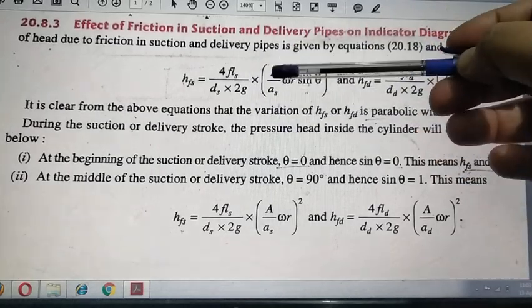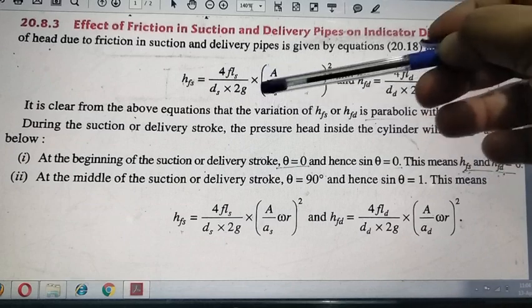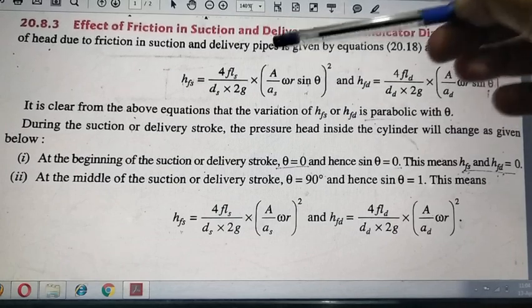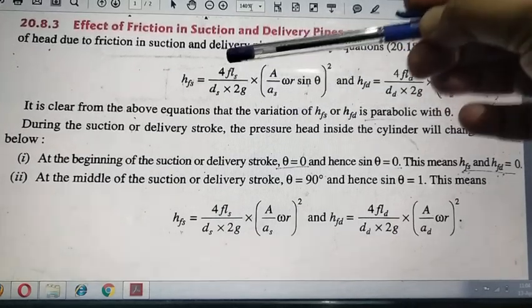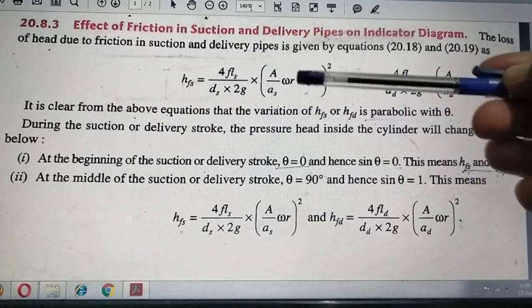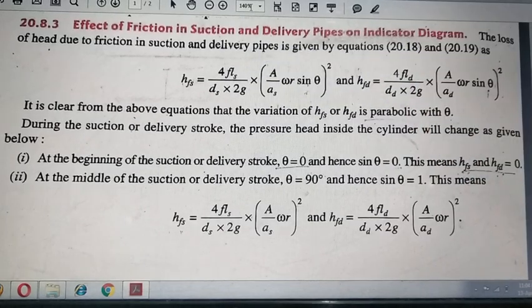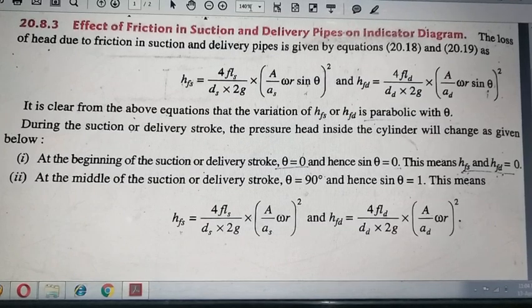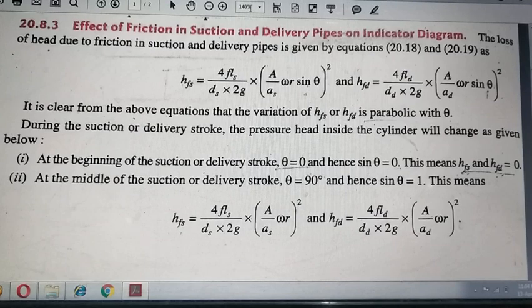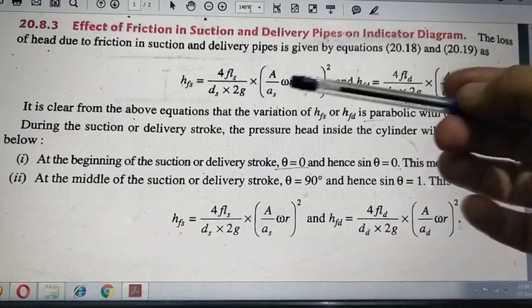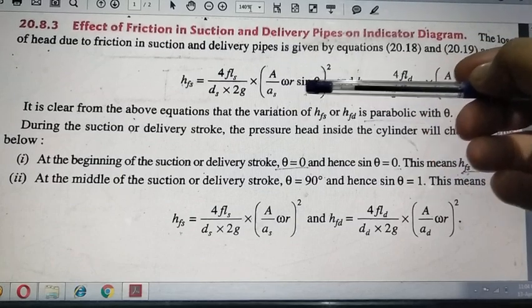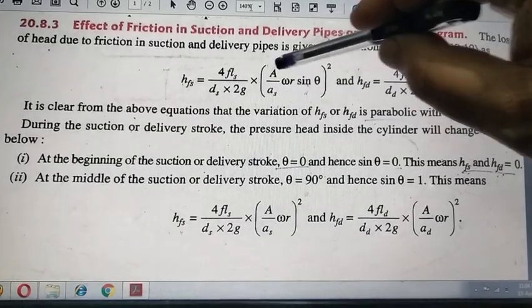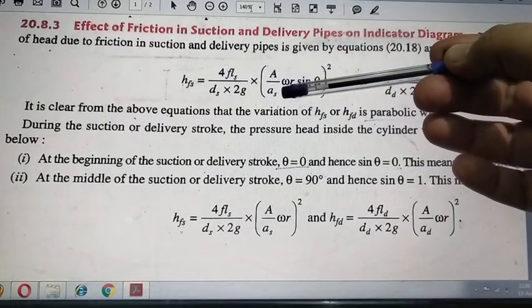The bracket term is capital A upon small as — that is the area ratio for the suction side — multiplied by ω·r·sin θ. In this equation, V² represents the velocity squared. The velocity due to the motion of the piston is (A / a)·ω·r·sin θ. So if I substitute this value for the suction side, we get the frictional head at the suction pipe.